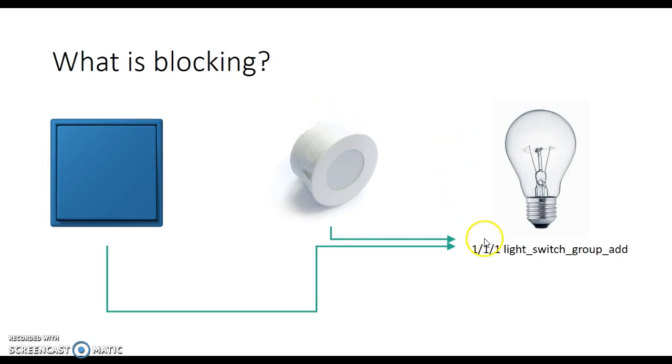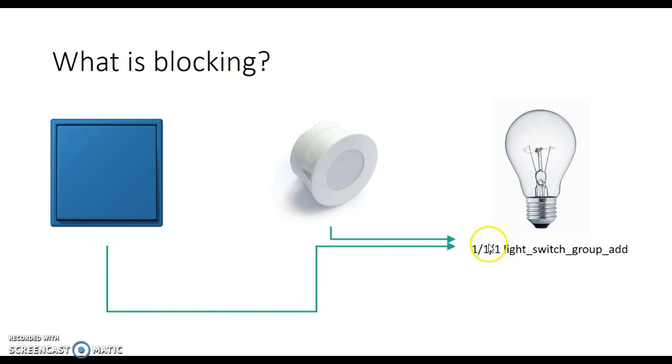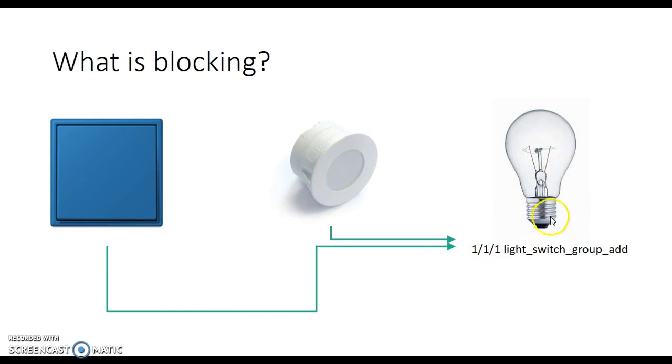Now if we typically set this up where we have the actuator for the light just feeding off one group address, in this case 1/1/1, and we can switch that on with the light switch and if this address gets a 1 then the actuator will come on, the light will come on. If this gets a 0 to this address then the light will go off.